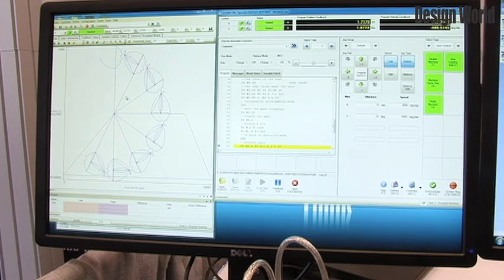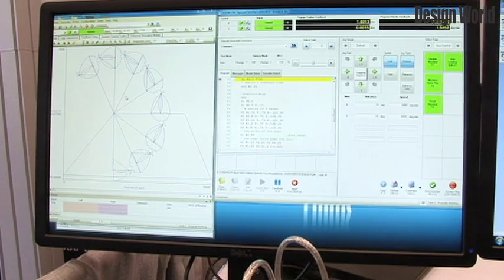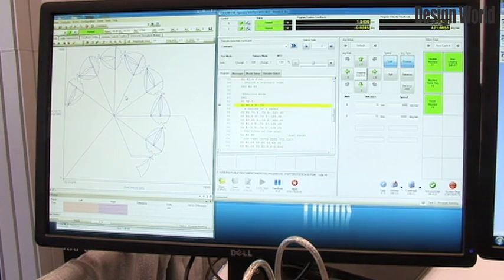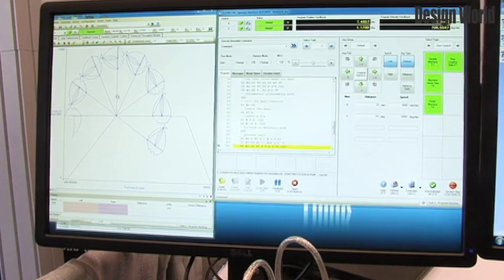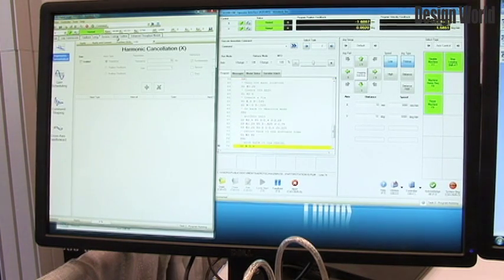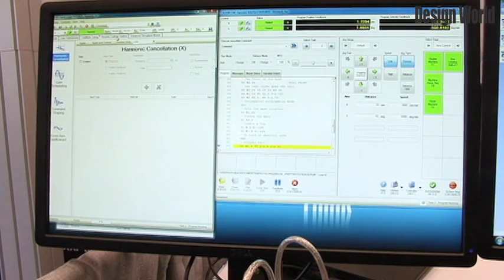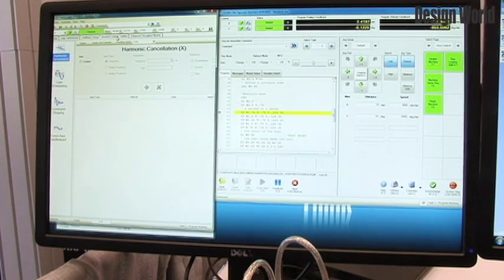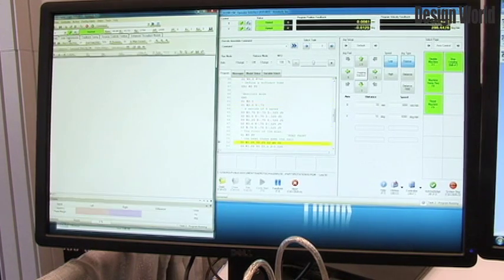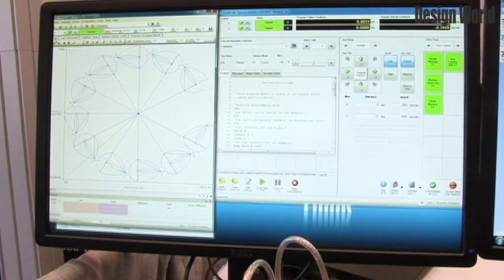On the left side panel you see the integrated scope tools which allow you to plot both PLC and motion variables on the same screen, as well as tools for enhancing the performance of the machine. We have a dynamic control toolbox that allows you to get better response in terms of point-to-point moves as well as coordinated moves, and other tools like feedback tuning and loop transmission tuning for inserting the various filters that you may need in your machine.